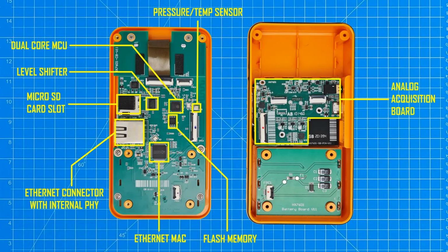Then there is the analog board. This is the actual business end of the radiation detection process. The sensitive circuits used in the detectors need to be separated from the noisy digital signals. Underneath the analog board is the pin photodiode module, and the electrical noise isolation requirements are even more severe for this component. Finally, there is the battery board, used to protect the product from the batteries being inserted the wrong way around.